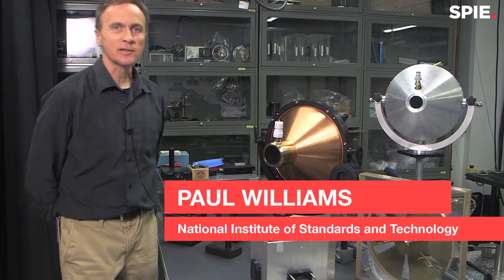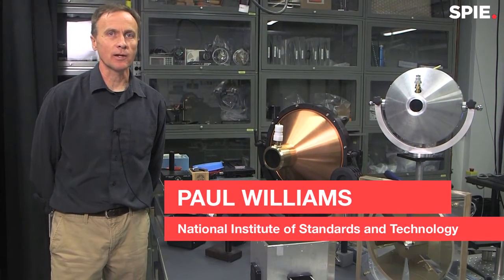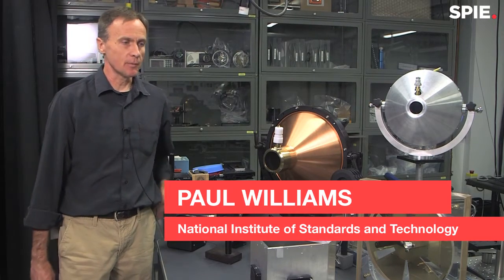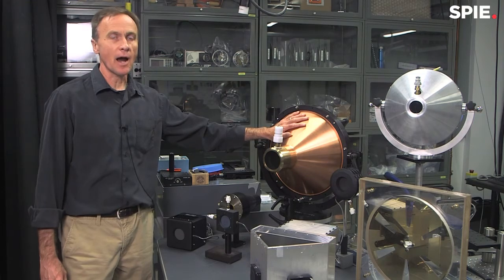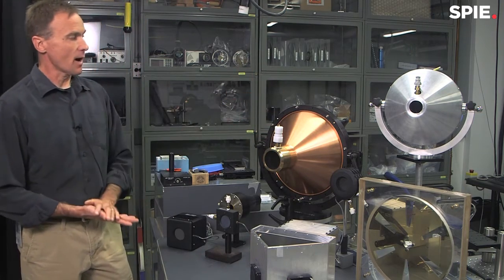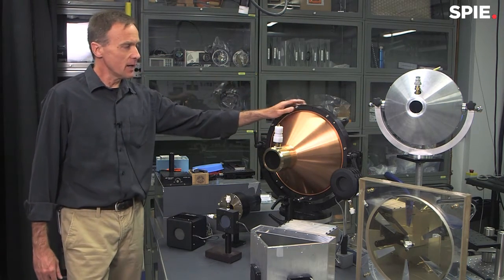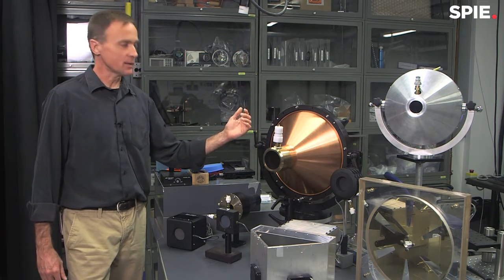Hi, I'm Paul Williams, a physicist here at NIST. I work in the laser radiometry lab as well. And I want to talk about instruments for measuring higher power laser power. This, for example, is a flowing water power meter. It measures up to 25 kilowatts.